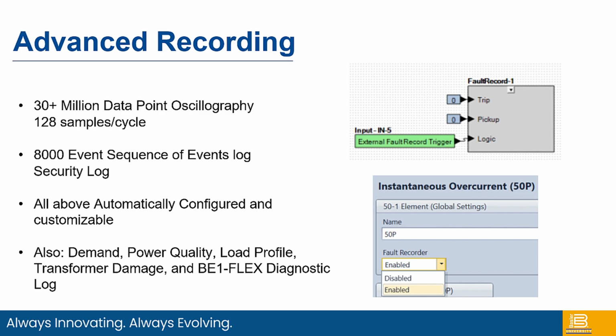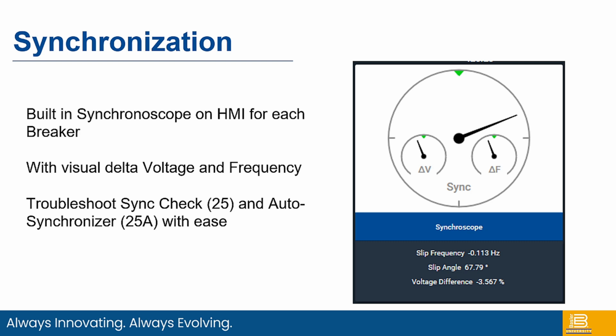So one of the things that's very helpful with digital protective relays is the ability to record information, but if it's not recording, if it's not turned on, then it kind of defeats the purpose. So we do a lot of these default enabled type things in the Flex, but also keeping in mind that we will never turn on a protective function because we're never going to put a set point in there, because we don't want it arbitrarily tripping, as opposed to arbitrarily recording information, which is harmless. It's just sitting in the relay and just logging information that may or may not be useful, may or may not be necessary, but it's there if and when it becomes necessary.